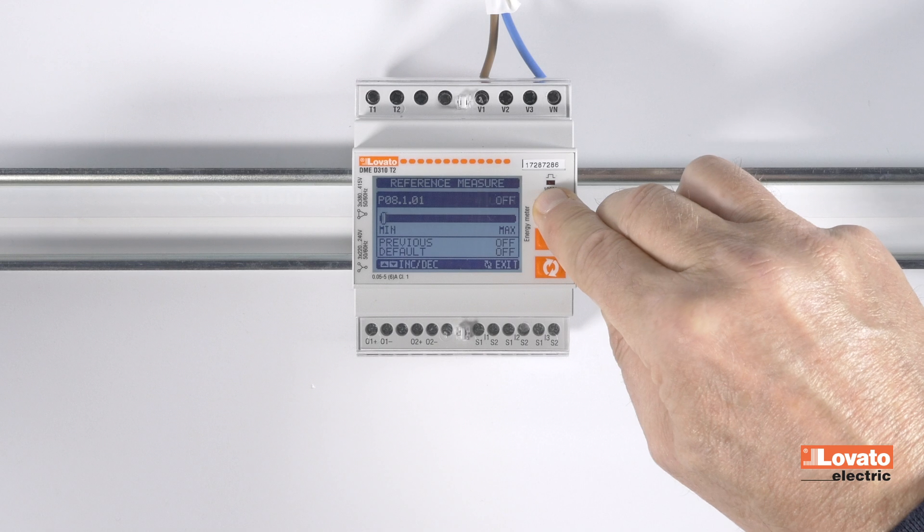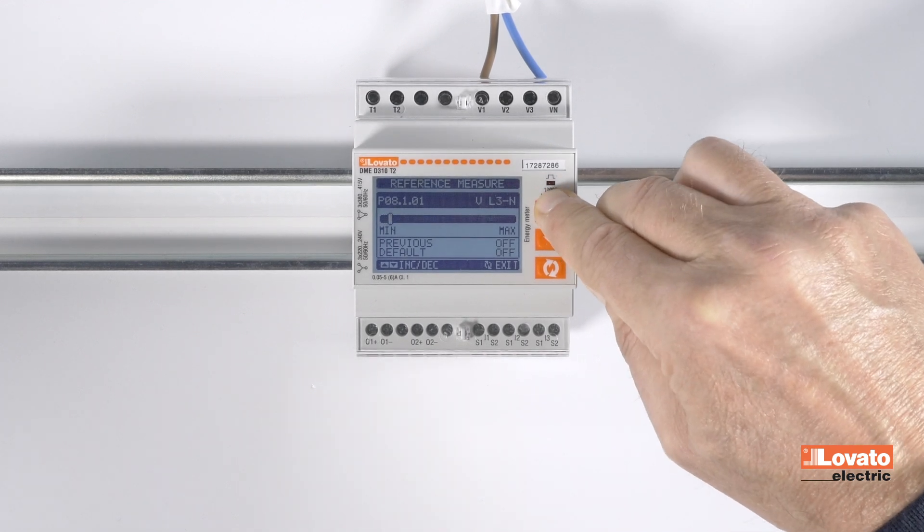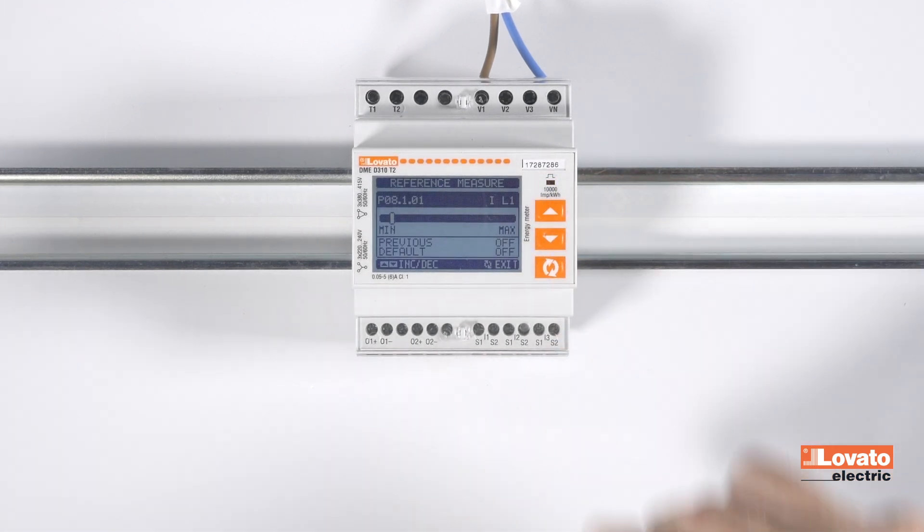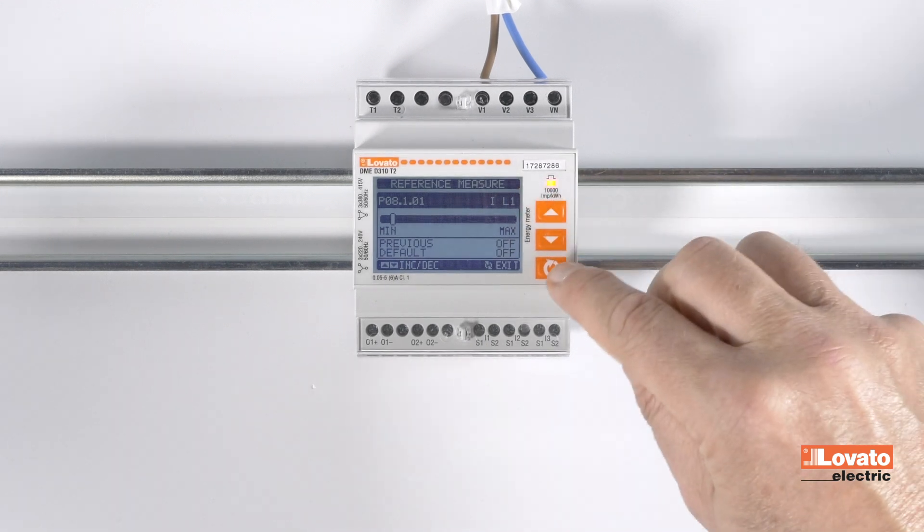Select the first variable limit shown on the menu and confirm. Confirm the choice of the reference measurement, current in Phase 1.